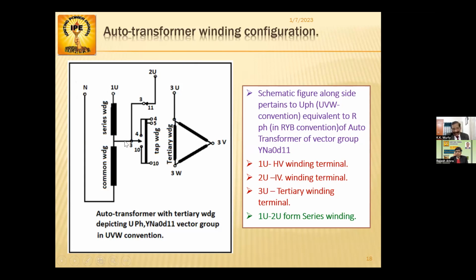So here you can see there are two windings, and from here the tap is the IV winding. 1U is the HV winding, 2U is the IV winding, the intermediate voltage, and 3U is the LT winding. This is known as the LT winding, which is the tertiary winding in an auto transformer. Here 1U and 2U form the series winding. Whereas this is the common winding. This is common for 1U, and this is also common for 2U.